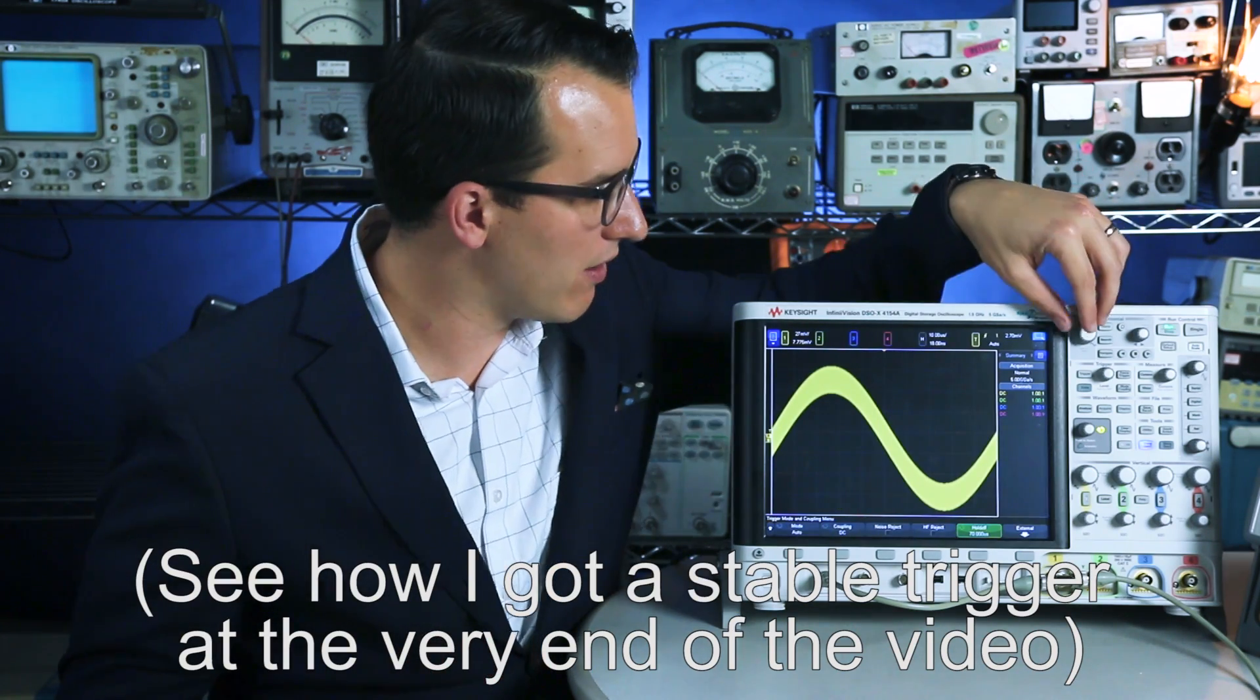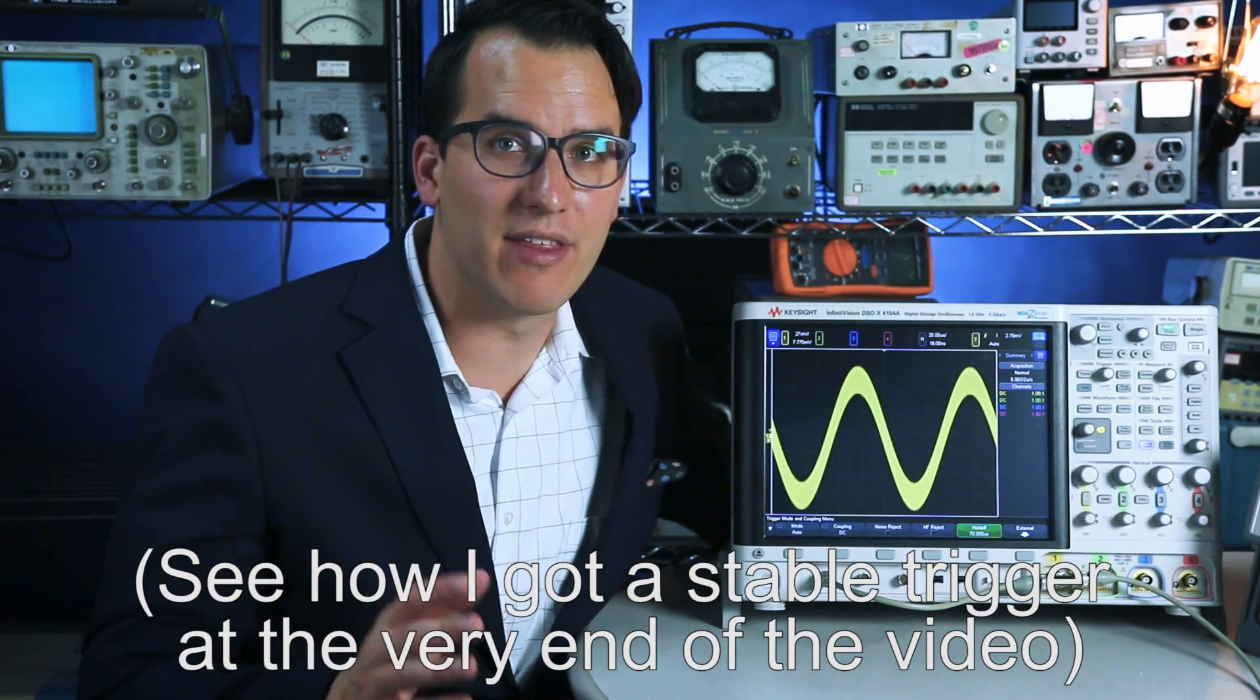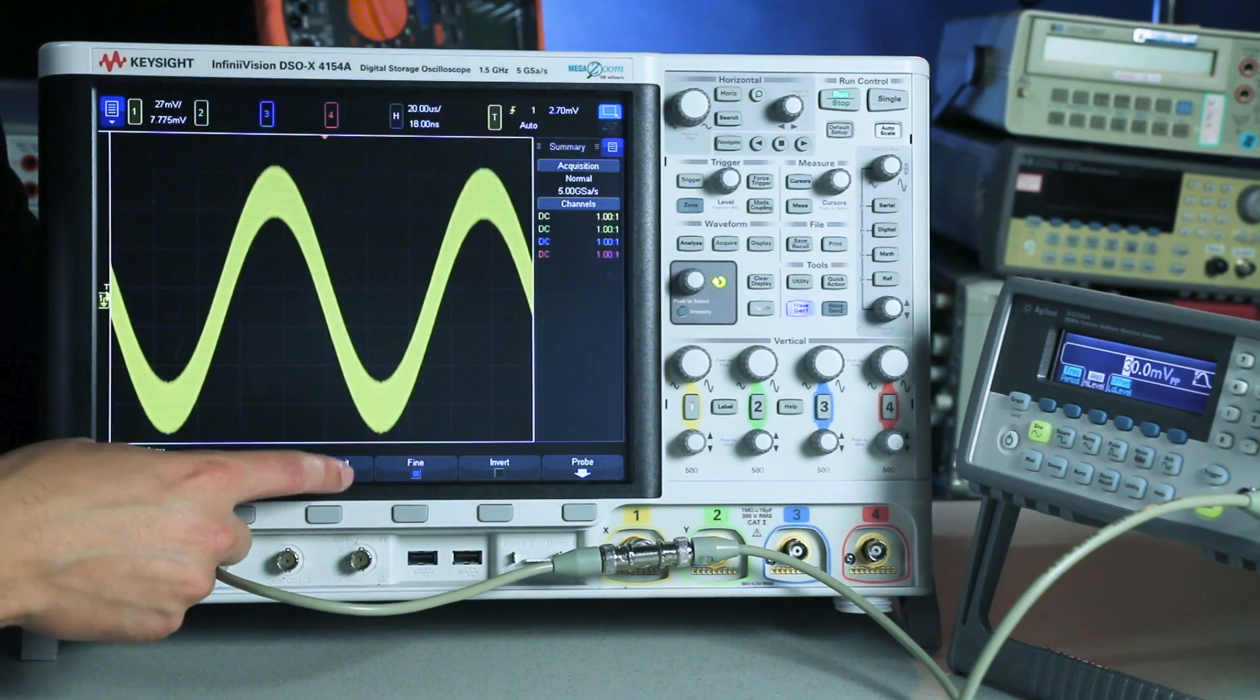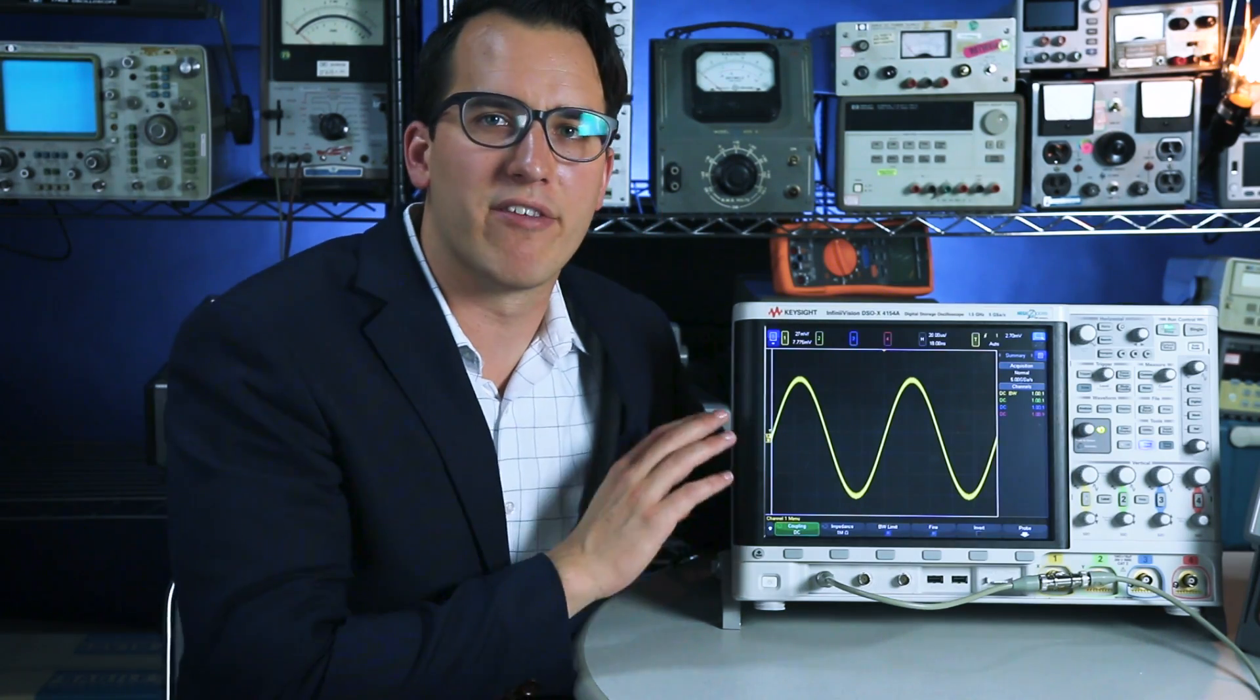So now that I have a stable trigger, let's zoom out a little bit and turn on bandwidth limiting. To turn on bandwidth limiting, I'm going to select the channel and I'm just going to turn on the bandwidth limit and I've now put in a 20 megahertz bandwidth limit on this signal.